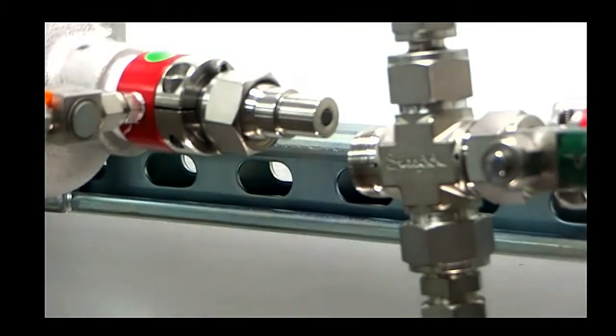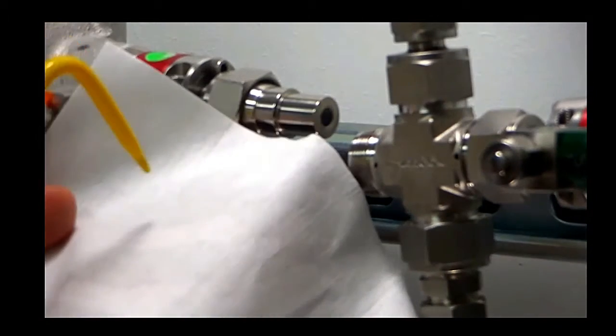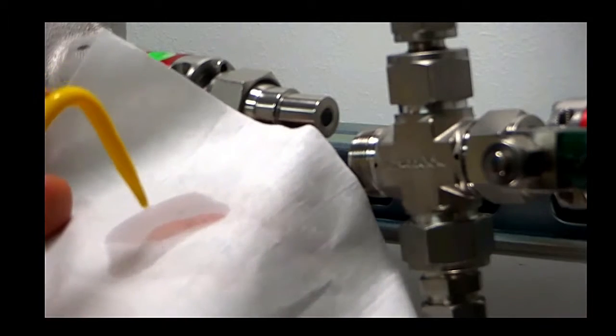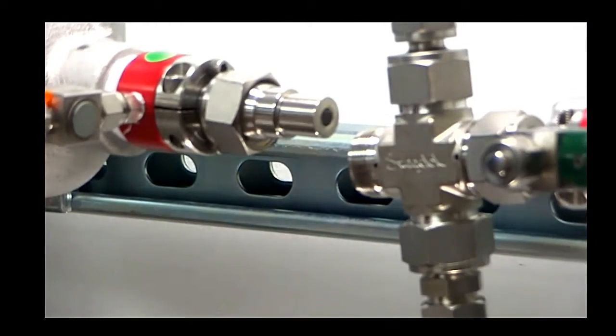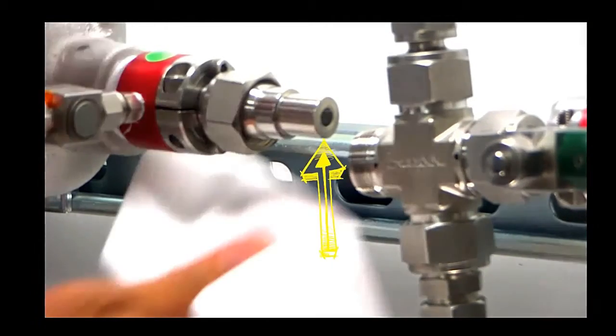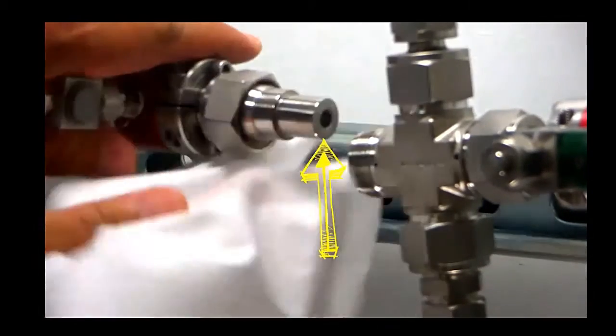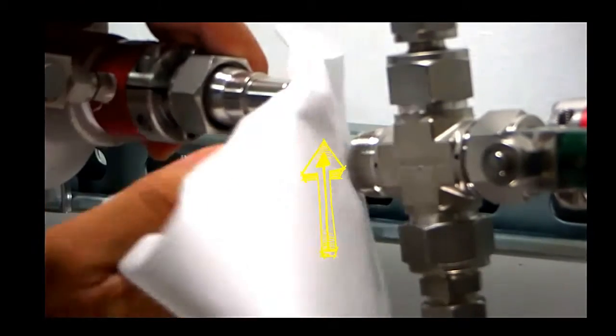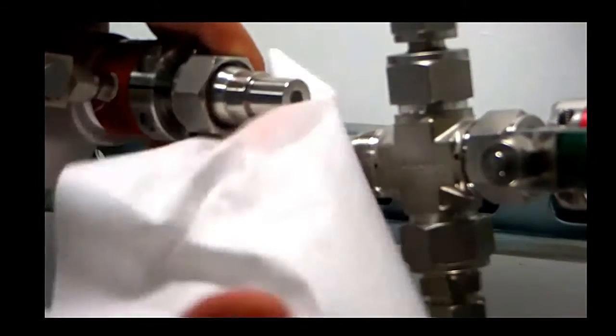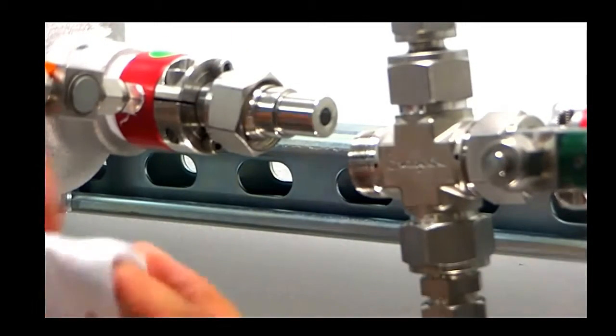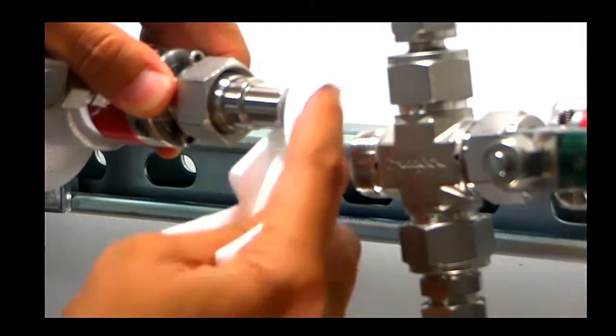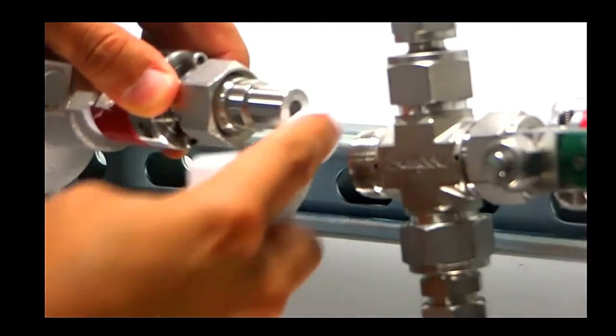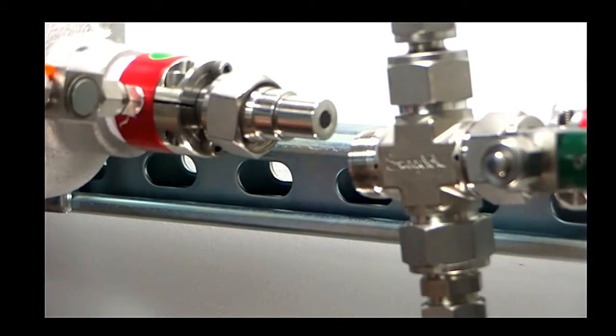Step 6. Cleaning the lenses. Using a microfiber cloth and a small amount of isopropyl alcohol, clean the surface of the lens. The lens is the central portion of the probe. It is a clear sapphire that is easily recognizable from the stainless steel fittings around it. It's also important to clean any residual material away from the probe itself, as well as the central cross.